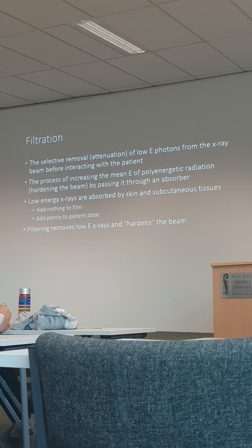Those low energy X-rays, if they weren't filtered out, would just normally be absorbed by your skin or your subcutaneous tissues. They don't add anything to the film, obviously, because they can't get through the patient, but all their energy is going to be added to the patient dose, so that's bad. And this is what we call hardening the beam.